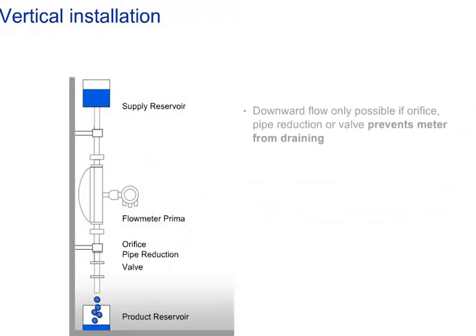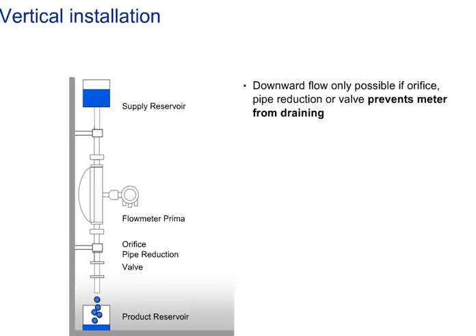Downward flow is possible with the introduction of an orifice pipe reduction or a valve preventing the meter from draining during normal running. Back pressure of 0.2 bar, which equals hydrostatic water pressure of 2 metres, must be assured to guarantee correct measurement.